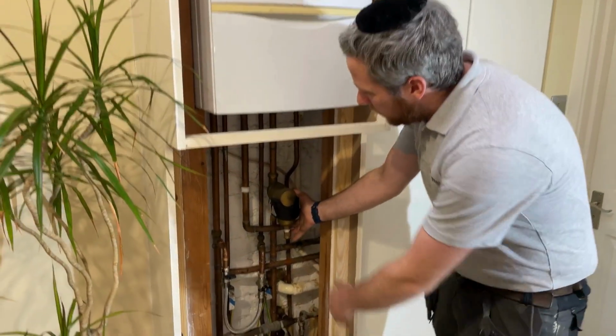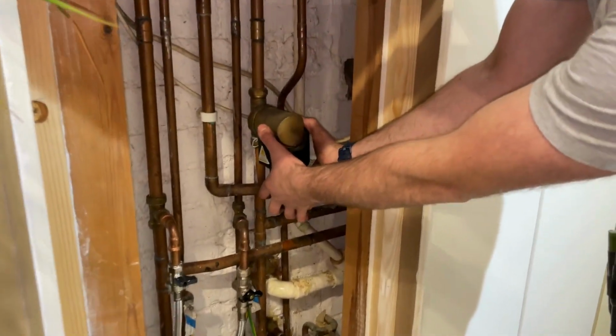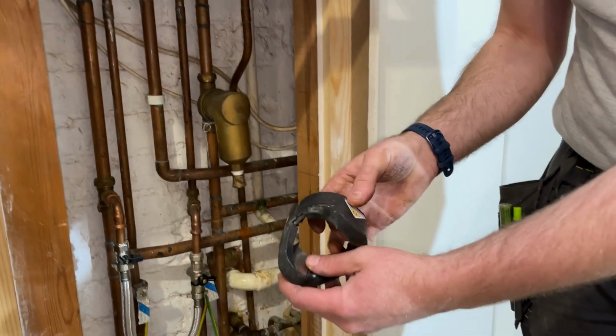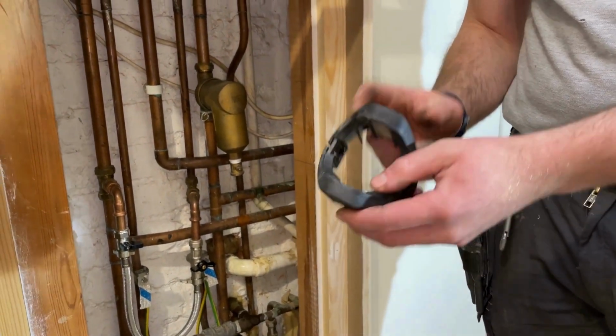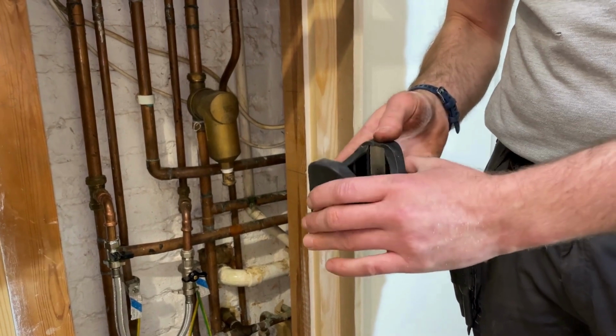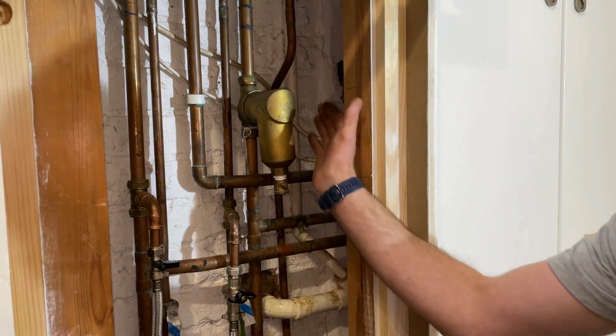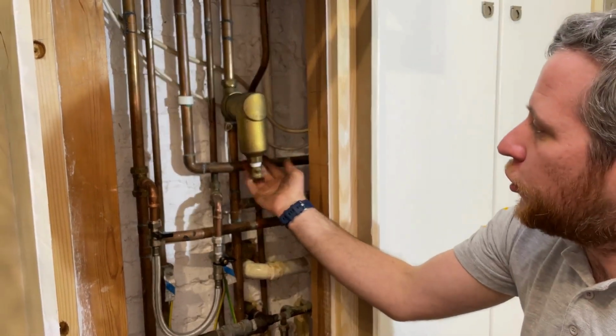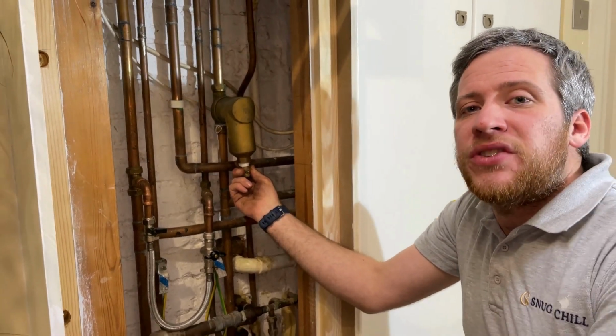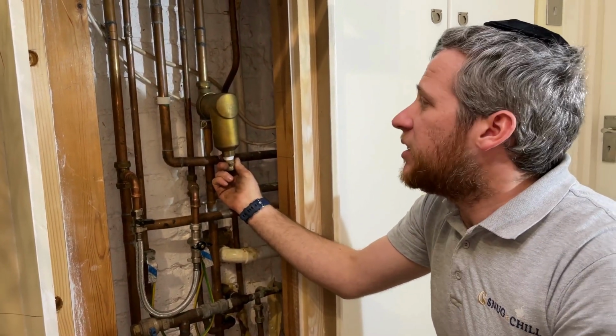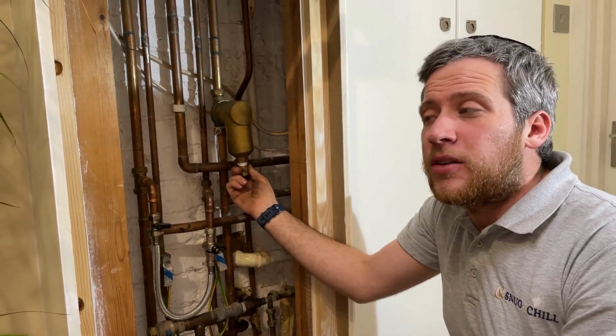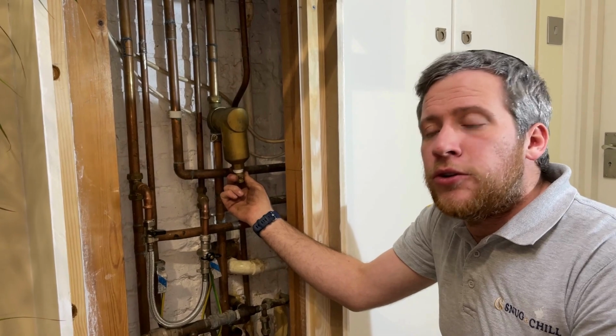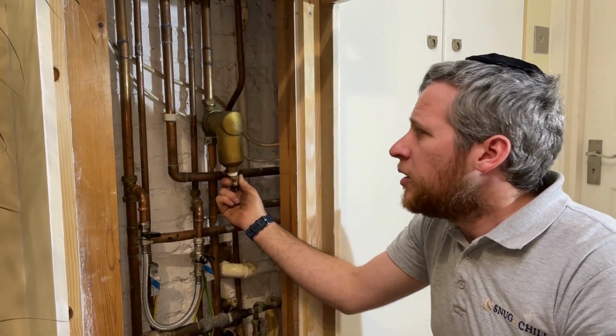As you can see, this black thing over here dislodges. So if you pull it down, on either side it has a magnet. Be very careful where you put this next to, because it's a very powerful magnet. Okay, so put the magnet down, and then what you've got is something called the brass body. In the brass body there could be a lot of debris at this moment. This debris is metal debris, and it's very common on dirty heating systems and systems which have been used for quite a while and not been power flushed, for dirt to build up. It's normal for a system to corrode over time, but not too much.